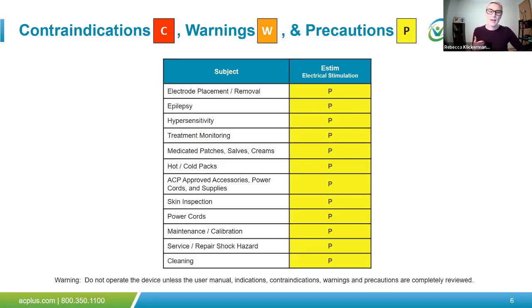And one point to make with the electrode placement is the electrodes should not be placed in direct contact or in close proximity, so 1 inch or less to each other during treatment. This can actually lead to high energy density and skin burns either under or between the electrodes. So we always want to make sure that there's that gap between the electrodes. Always make sure you're not just pulling the electrodes off of the skin, you're really walking your fingers down as you're gently removing the electrode from the patient's skin.